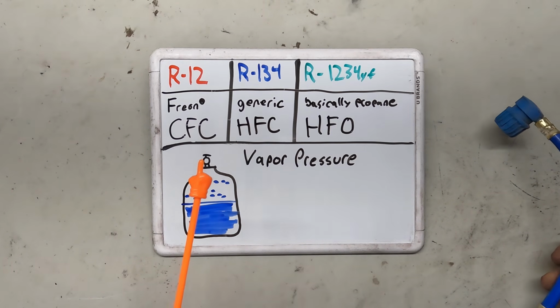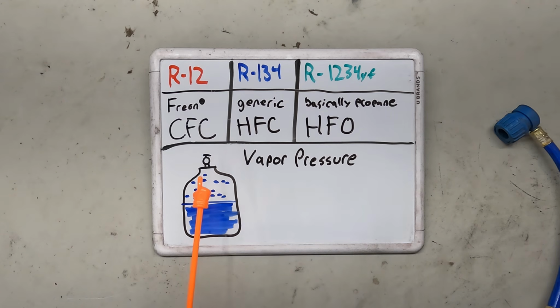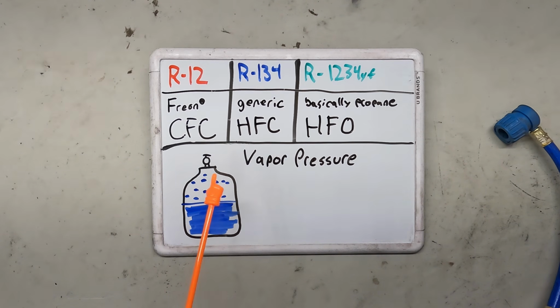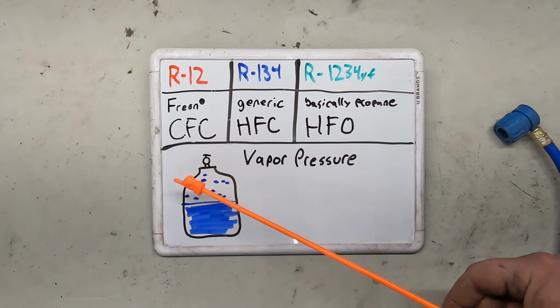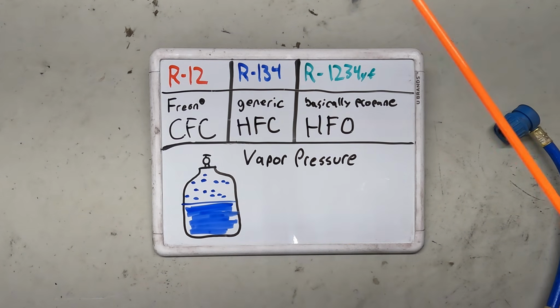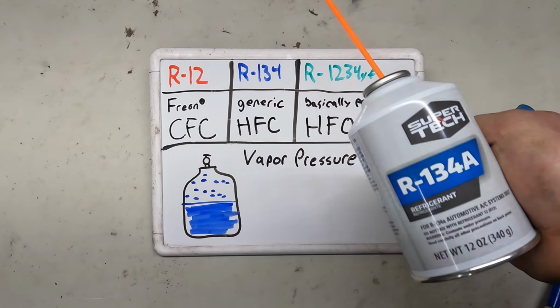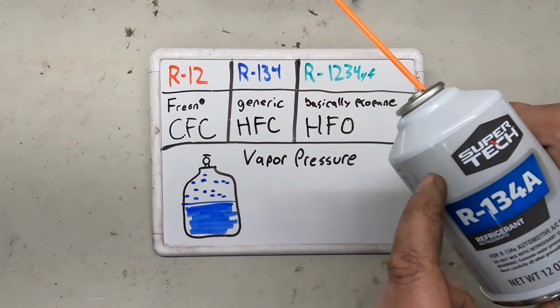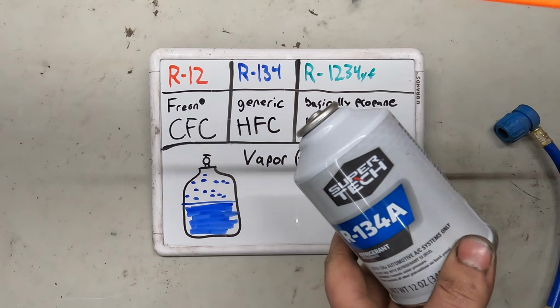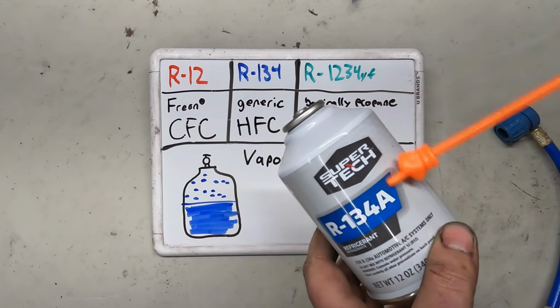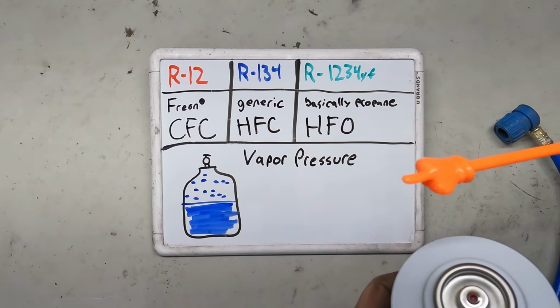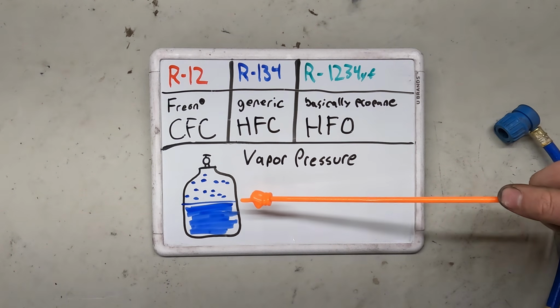So the only thing you really need to know about vapor pressure is that if you have refrigerant in a container, no matter how much physical refrigerant is in there, it's always going to be vaguely the same pressure. That pressure varies based on the temperature of the container. At room temperature, the vapor pressure of 134a is roughly like 70 pounds. So regardless of how full the can actually is, if there's any 134a in there, it's going to be that same 70 pounds.